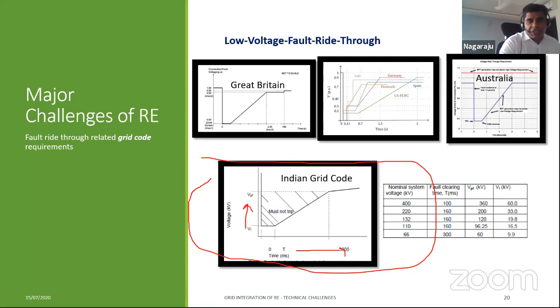If at the point of connection where we are connecting the renewable energy, the voltage is above this solid line, the machine has to be still running, operational, and should not get disconnected. Below this, it can disconnect. So in India, as per the Indian grid code, if it is a 400 kV system, the voltage can go as low as 60 kV at the connection point. And if it is a wind turbine, the wind turbine should still continue to operate and provide the reactive current to support the voltage.